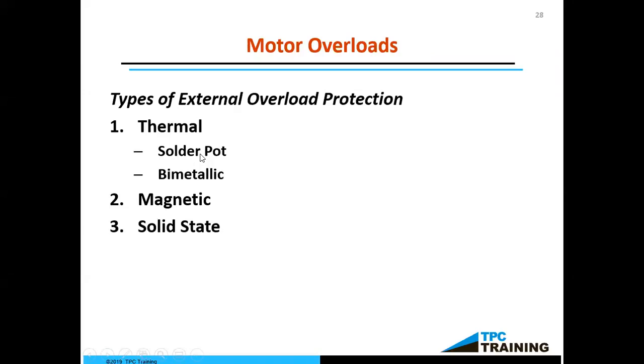Solder pot, where we have a little chamber that is filled with solder that will melt if it gets too hot. And when it melts, it's going to trip a switch that will shut off our coil on our motor starter. Or they could be bimetallic, and too much heat flows through, and that could open up those two pieces of metal and prevent the motor from overheating. Or we could have some magnetic sensors, or in the case of a variable frequency drive, they could all be solid state sensors. So electronics could help us with that motor.